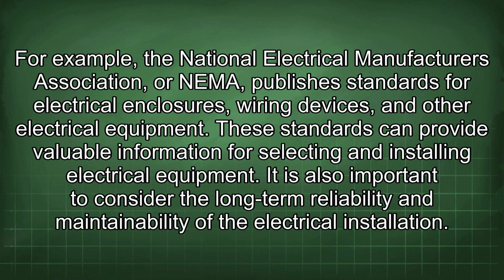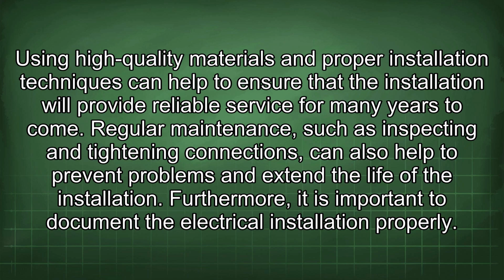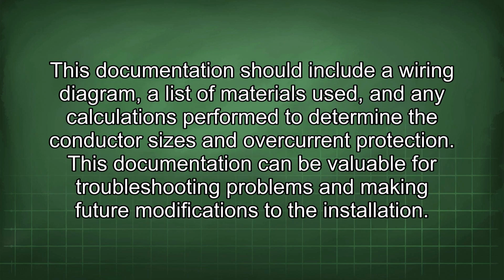It is also important to consider the long-term reliability and maintainability of the electrical installation. Using high-quality materials and proper installation techniques can help to ensure that the installation will provide reliable service for many years to come. Regular maintenance, such as inspecting and tightening connections, can also help to prevent problems and extend the life of the installation. Furthermore, it is important to document the electrical installation properly. This documentation should include a wiring diagram, a list of materials used, and any calculations performed to determine the conductor sizes and overcurrent protection. This documentation can be valuable for troubleshooting problems and making future modifications to the installation.